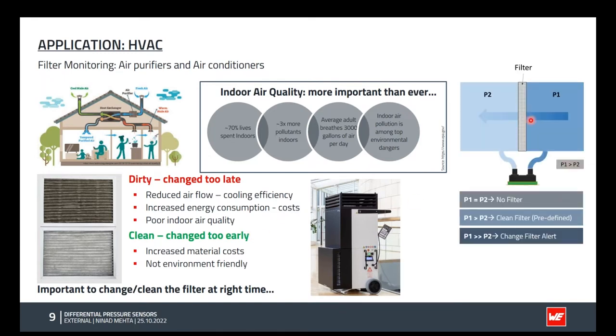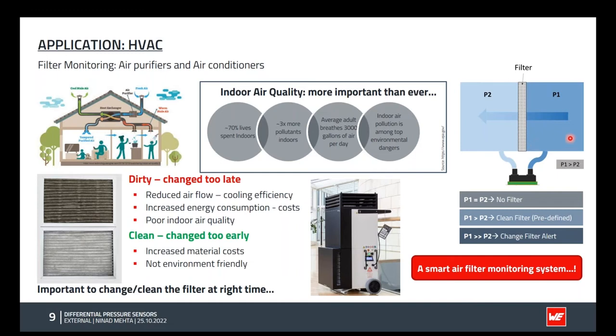So a solution would be to use a smart filter monitoring system where you have a differential pressure sensor connected to both ports on either side of the filter. And whenever the filter is clogged, there is a very high pressure difference between the high pressure side and the low pressure side. So here at P1, the pressure starts to build up, and after a certain threshold, the sensor will alert the microcontroller or the system that it's time to change the filter.